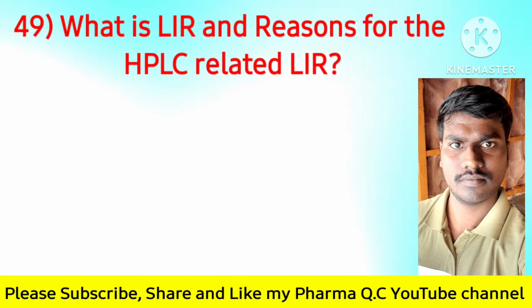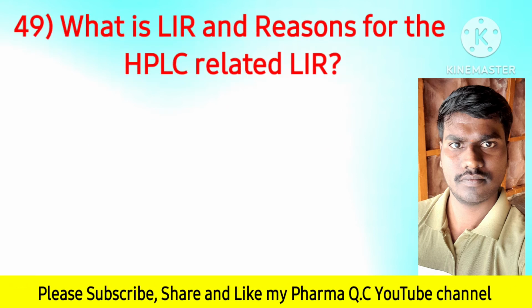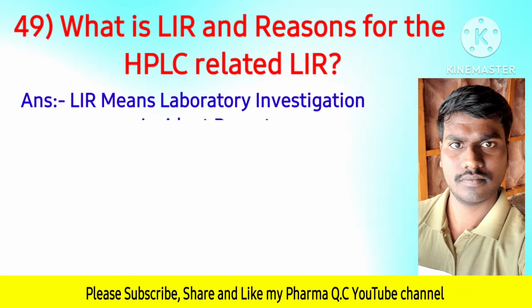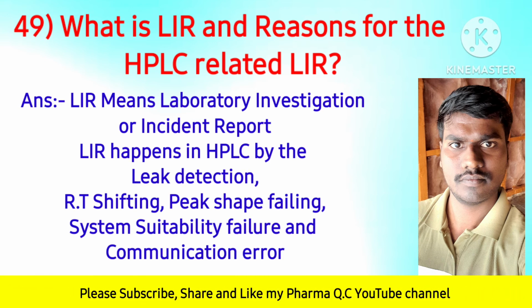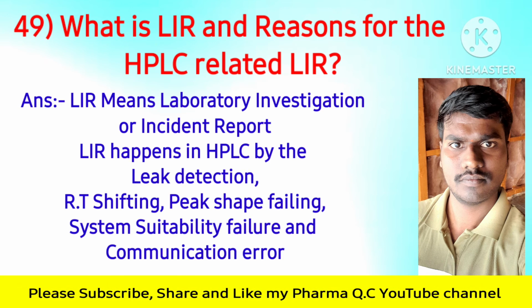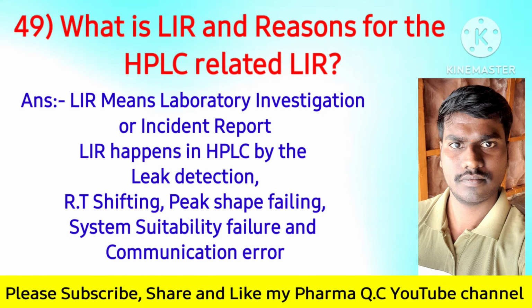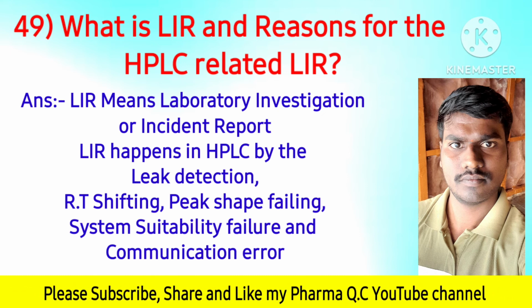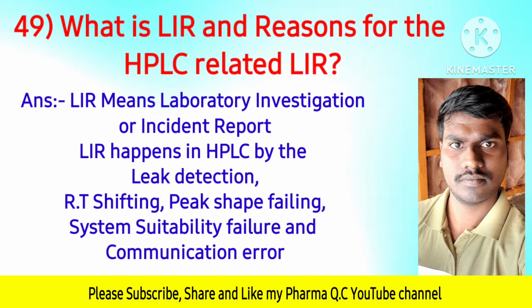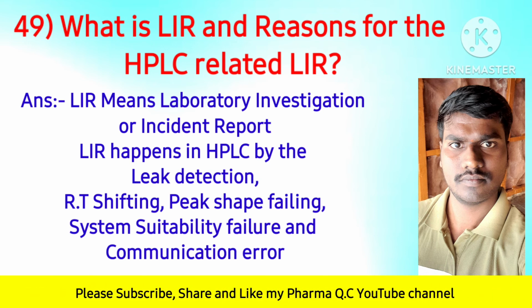What is LIR and reasons for the HPLC related LIRs? Answer is LIR means laboratory investigation or incident report. LIR happens in the HPLC by leak detection, RT shifting, peak shape failing, system suitability failure and communication error.